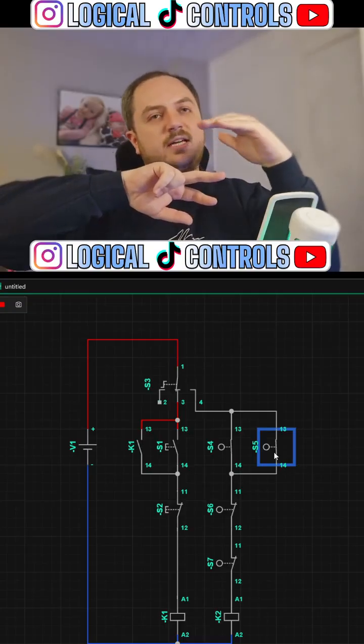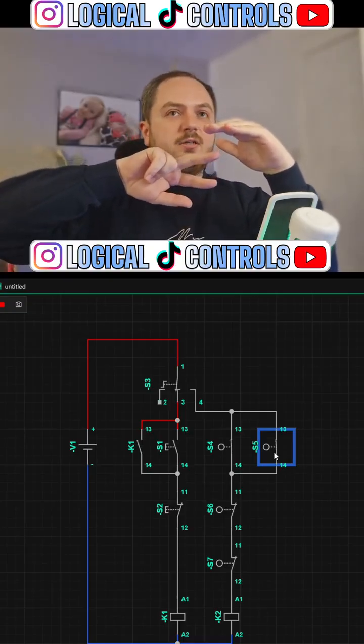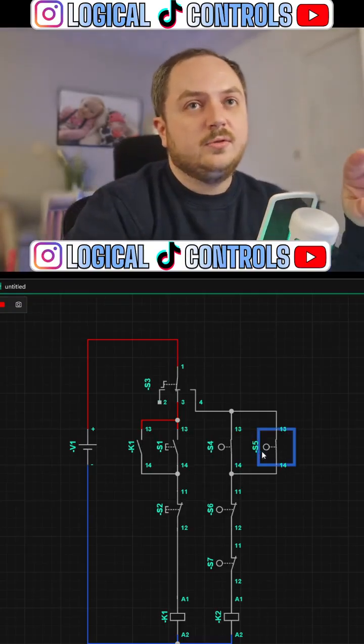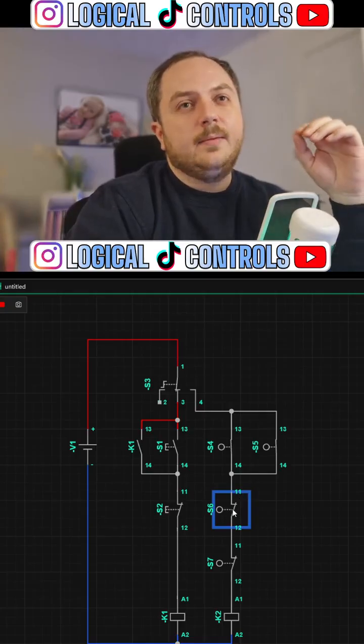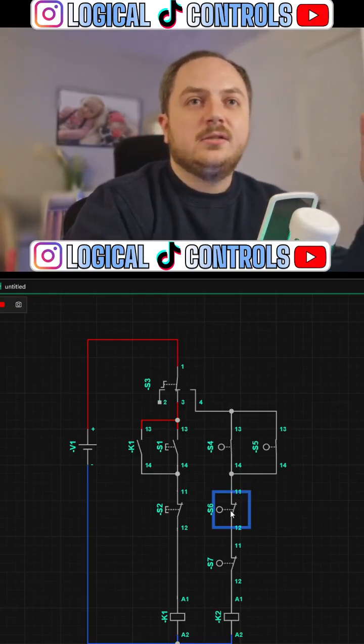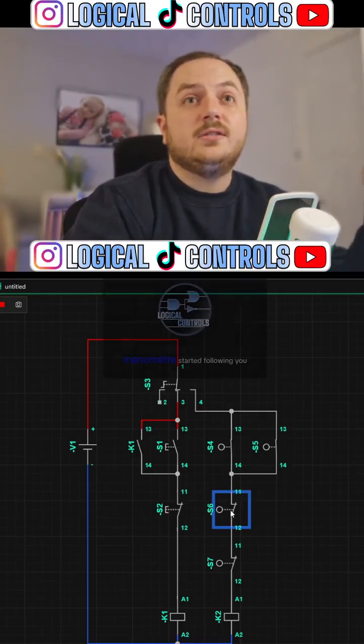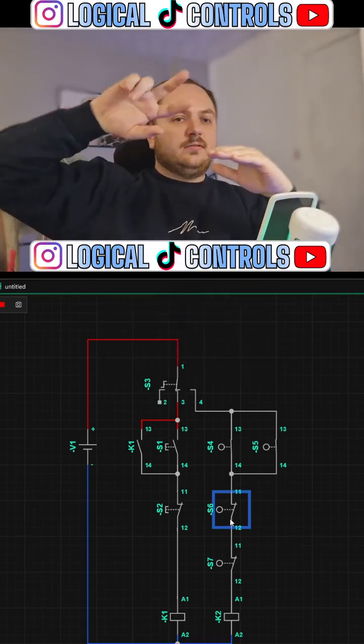So yeah, we've got this half full tank, and both of the 2 switches, we've got a low and a low-low, a high and a high-high. The low and low-low make on rise, so as the fluid level comes up, they close. The tank rises, those 2 contacts close, so that's why we're closing them too.